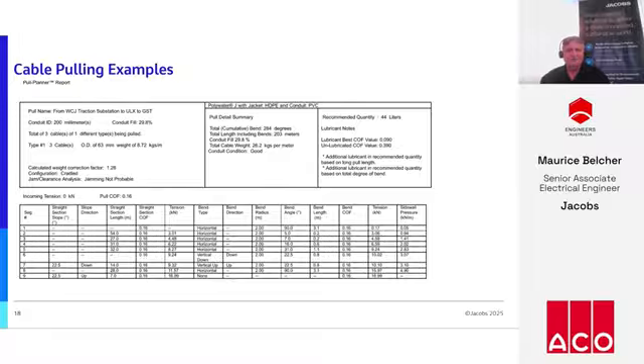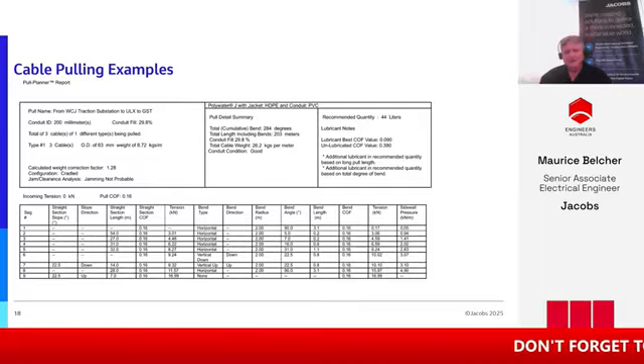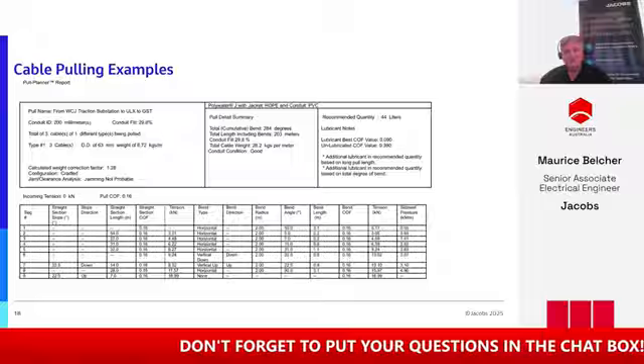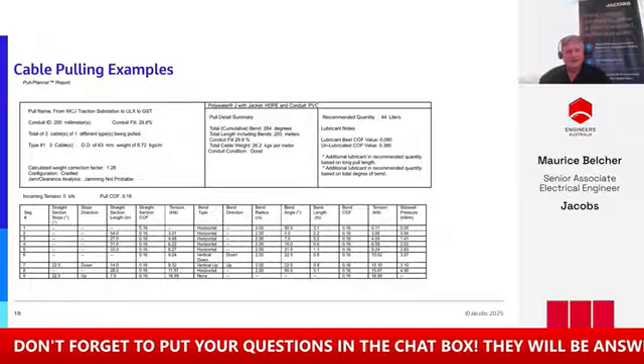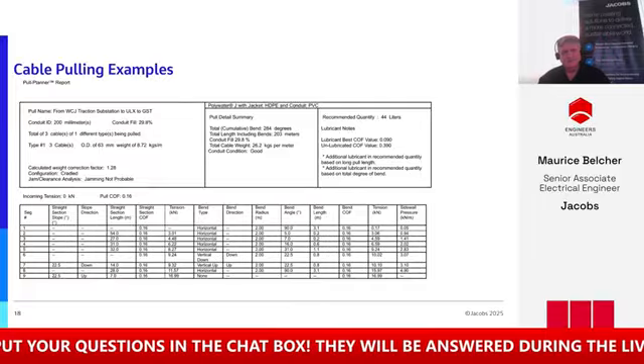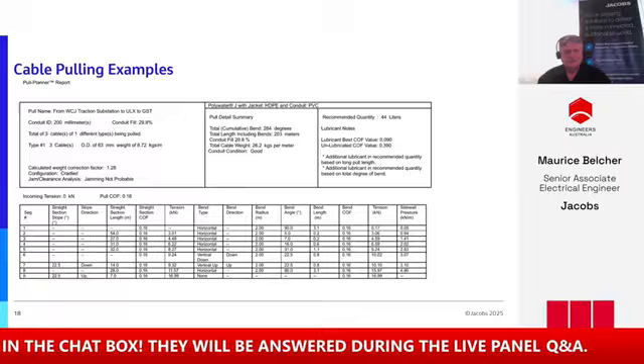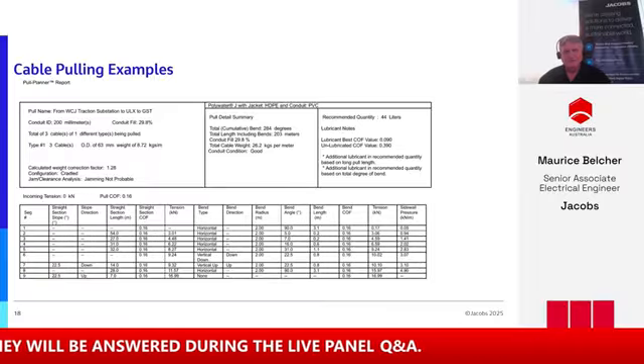Here's an example of the cable pulling software I mentioned. I'll confess I personally don't use this software, but there are people within Jacobs who do. This is ideal for very large cables that are typically high voltage and very heavy. The principle is to understand exactly how you're going to pull these cables, how many bends there are, how the coefficient of friction works, and how much tension is involved - you don't want to damage your cables when pulling them in.